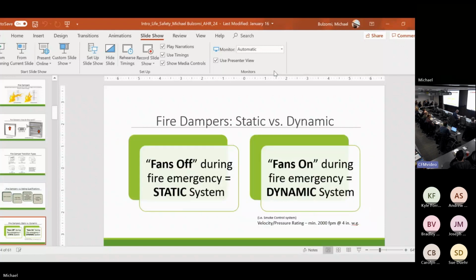So let's talk about static versus dynamic. Static systems, easiest way to remember this. A static system, the fan turns off in a fire emergency. There's a fire, a smoke alarm, building management system, fire alarm panel, something sends a signal and tells the main unit and the AC to turn off. There's no airflow going through my ductwork. That damper closes under still air. There's no velocity, there's no pressure. A damper can close pretty easily.